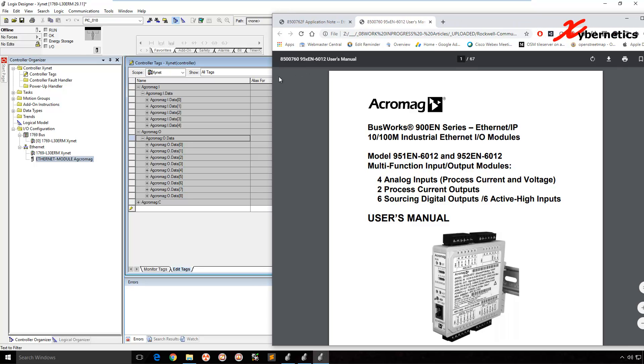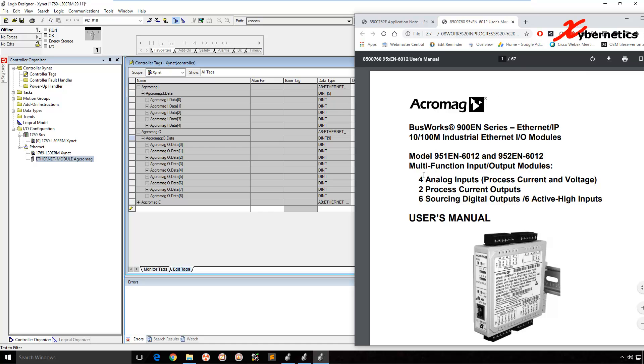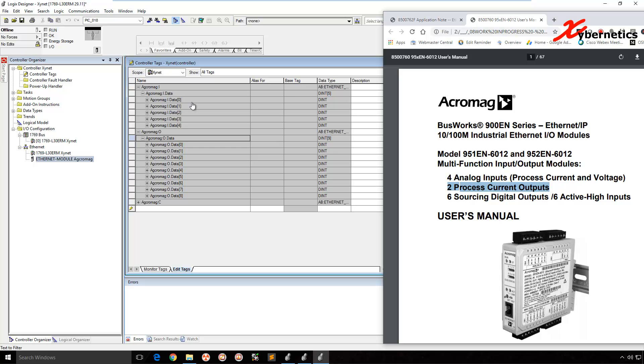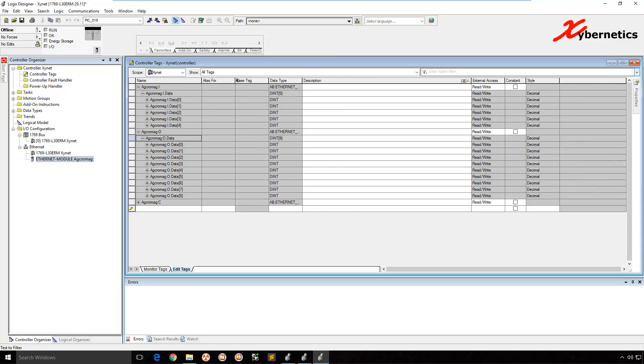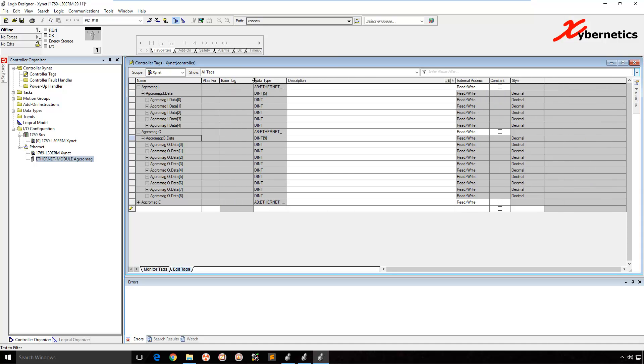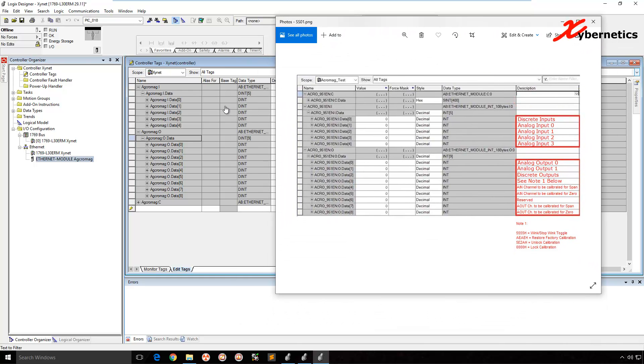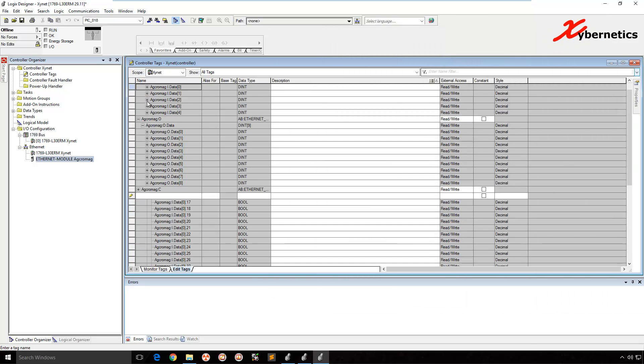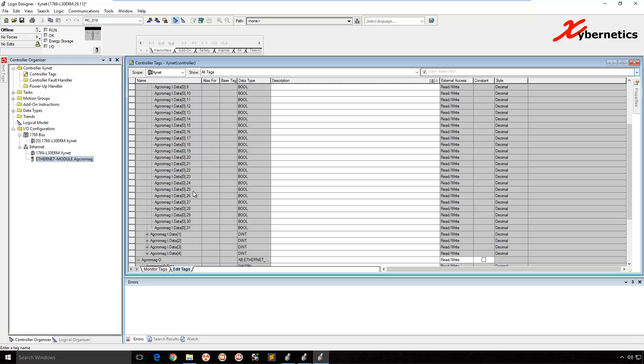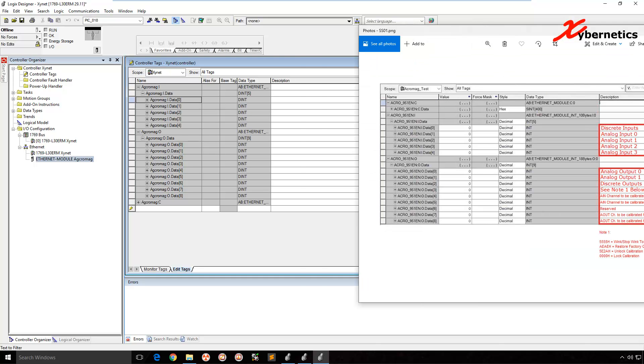So I'm going to expand this guy here and talk a bit about the input and output in particular to this AcroMAG module here. Again, going back in here, I did say that it has four analog inputs and two AOs. But you can see that over here in the array, it's got zero to four, which means altogether it's got five inputs and nine outputs. How is it? So I spoke to a technical support team there. And this is what they told me. This is their data map. So starting with array element zero is your discrete inputs. So it goes from zero to 31, which is 32, 32 bits altogether. The first, so this one has eight digital input, I think. So it goes from zero to seven is what they use or what you have to look out for. So that's your digital input.